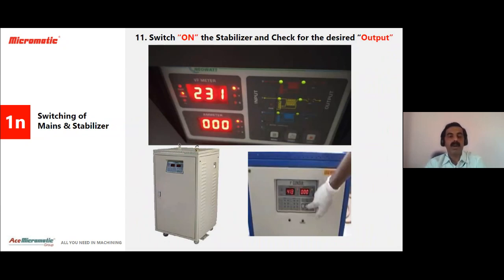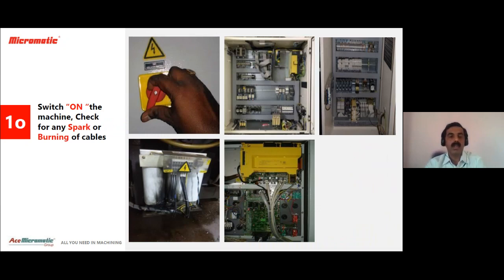After switching on, we have to switch on the machine. The machine switch is shown in the photograph. We have to switch on that switch. Before switching on, we have to check in the panel. So we have to keep the panel open so that if there is any problem in the panel after switch on, we can switch it off again to rectify the problem. This is as shown in the picture. We have to check, is there any short circuit? We can immediately address that short circuit so that further damage can be controlled.